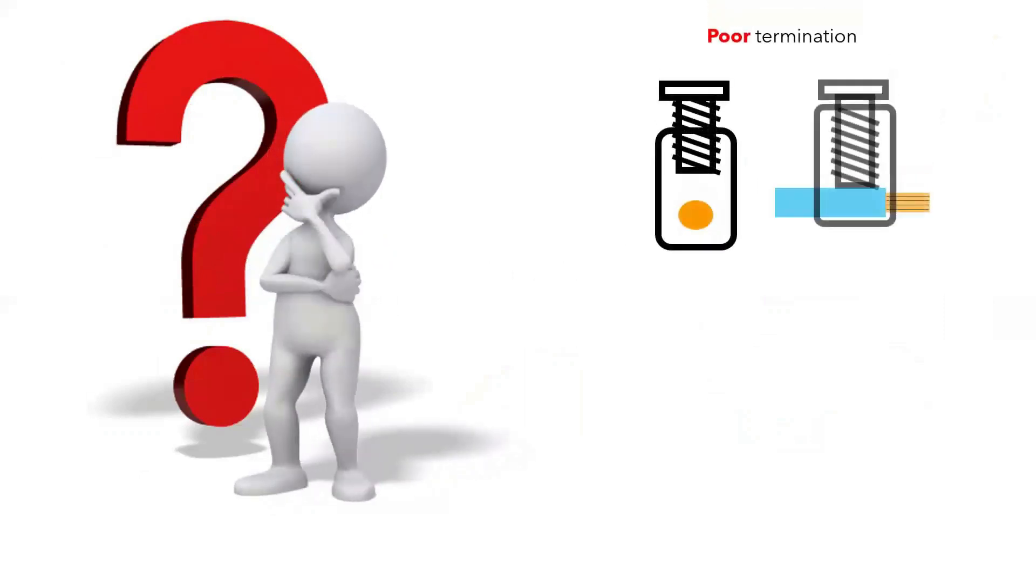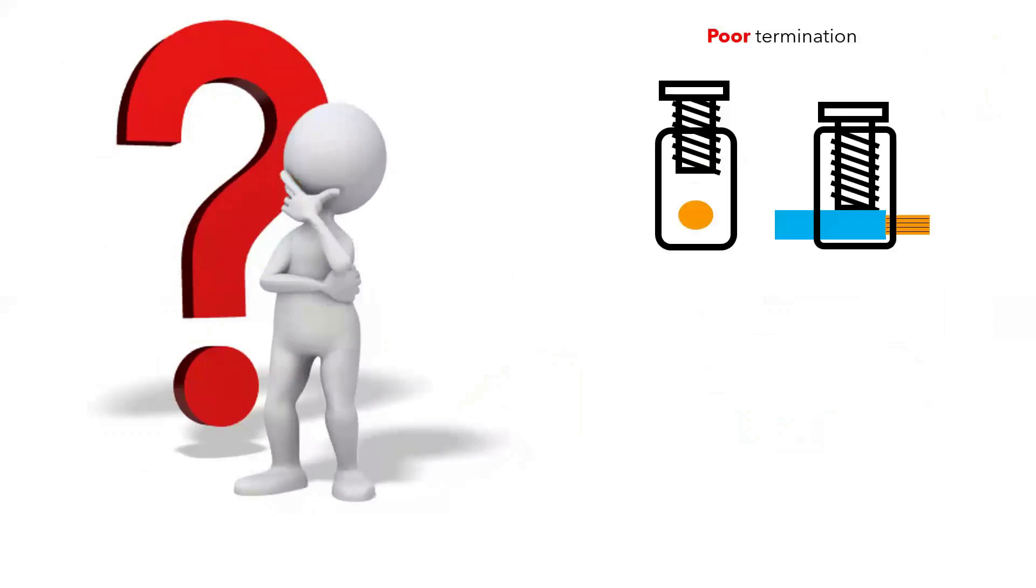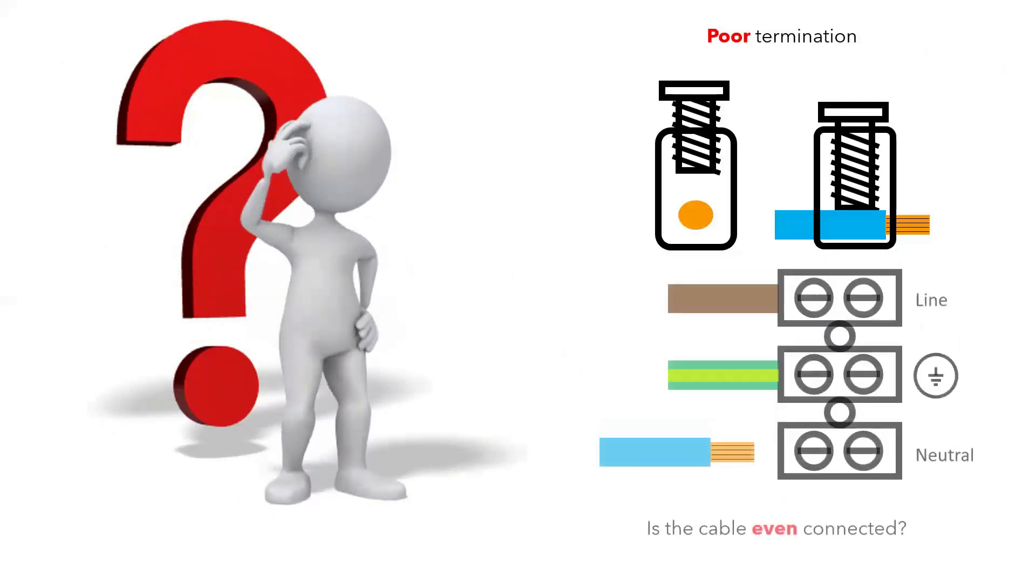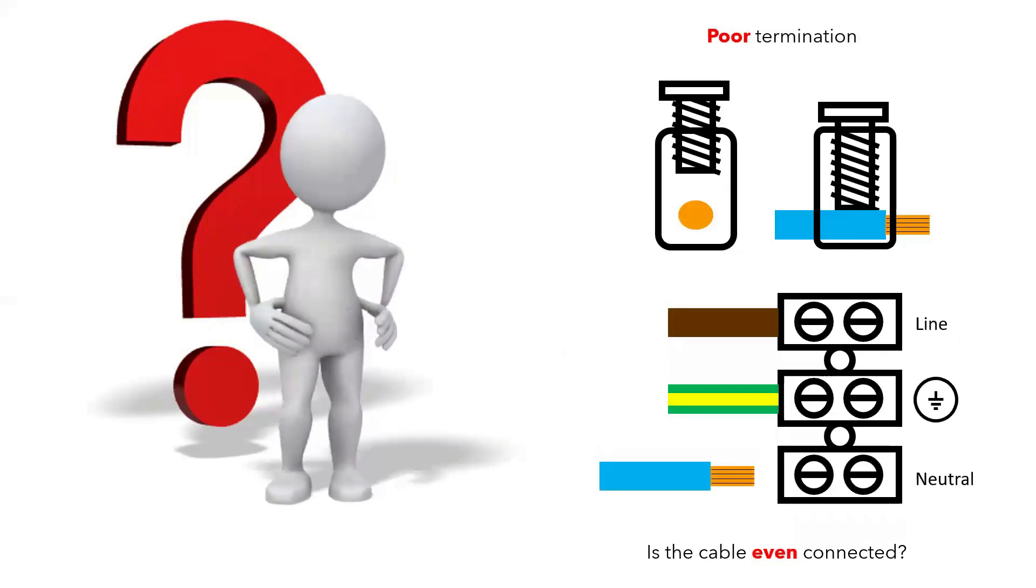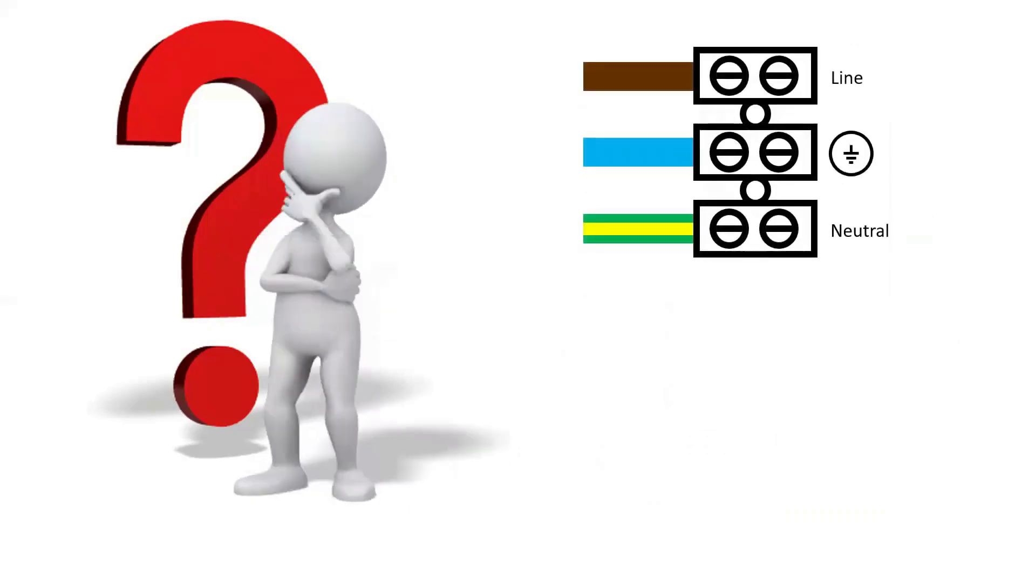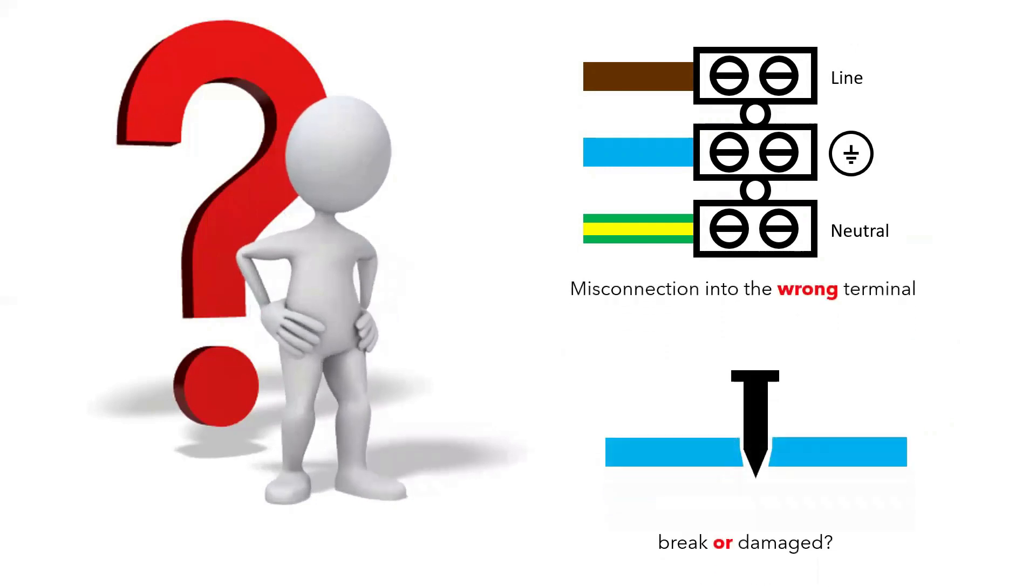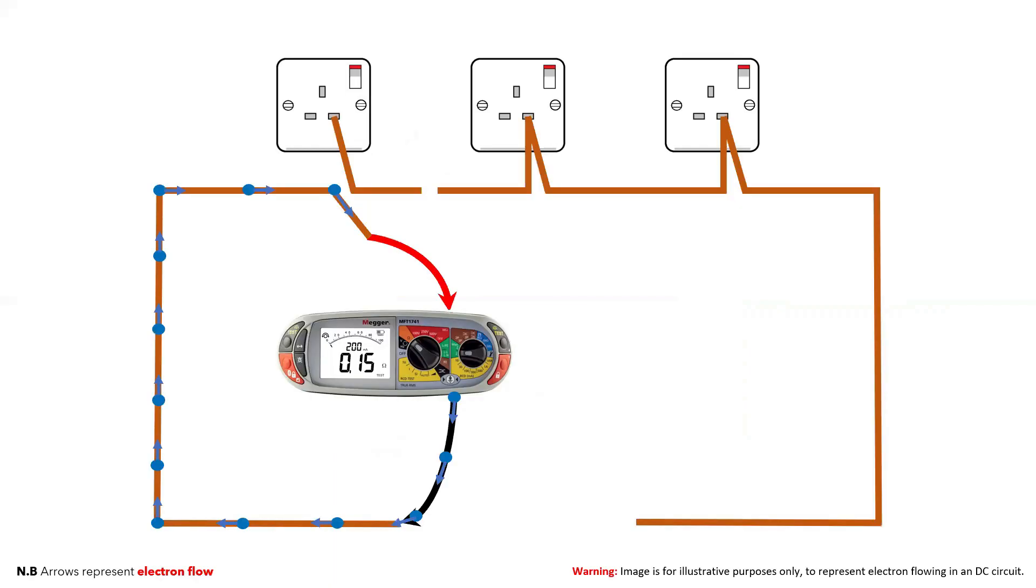Once you have established that the meter is working correctly and that it's not user error, then you can start to consider the possibilities and investigate these one at a time, starting with the most logical and easiest to rectify. For example, is it a poor connection that needs tightening, is the termination clamped onto insulation rather than copper, has the neutral come out or snapped, is it a misconnection, or is there potentially a break in the cable? A lot of these can usually be found by testing the individual legs of the ring to find which two points the fault is between.